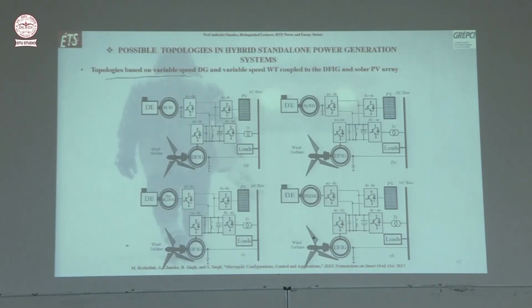Topology is based on variable speed diesel generator, variable speed wind turbine coupled to DFIG, and solar. So you see, again, the wind turbine, doubly fed induction generator, rotor side 1/3 capacity AC to DC converter, but then on this DC bus, diesel engine output is coming and also PV output is coming on the DC bus. So the size of this inverter will increase to take care of this power and this power also. So you are having a variable speed diesel generator here.